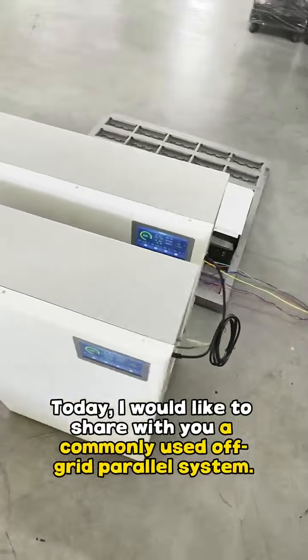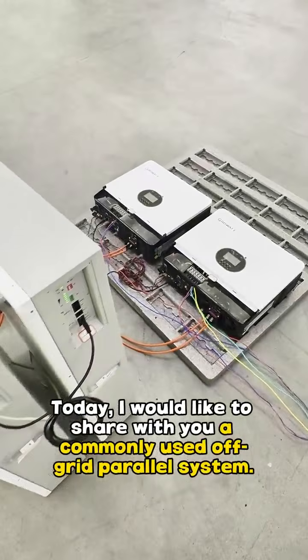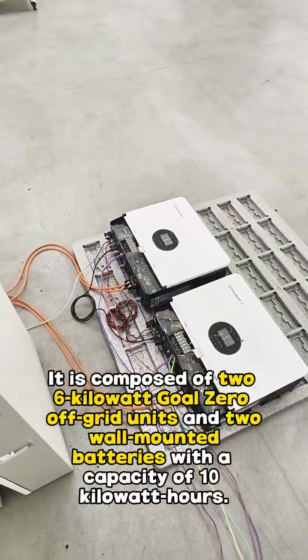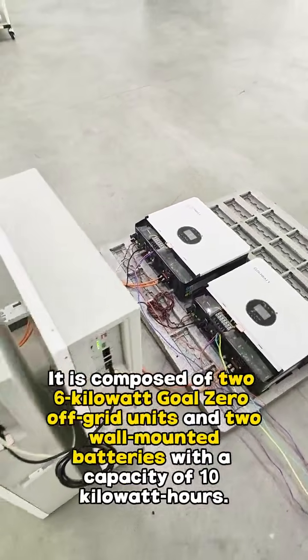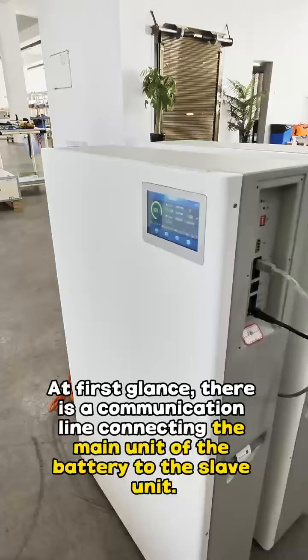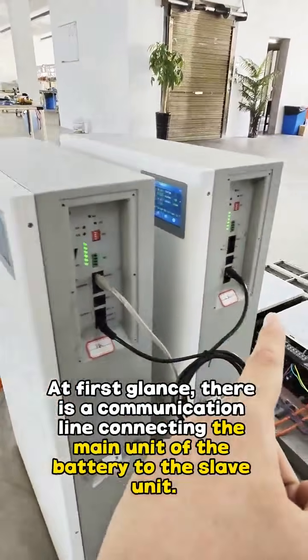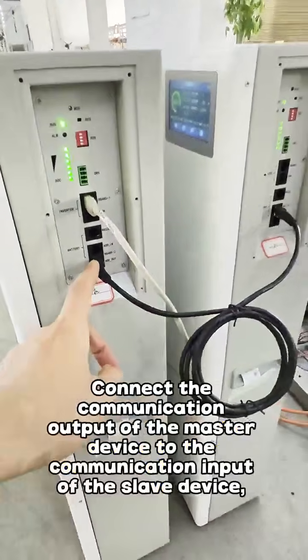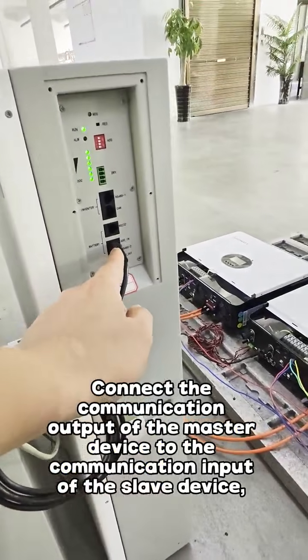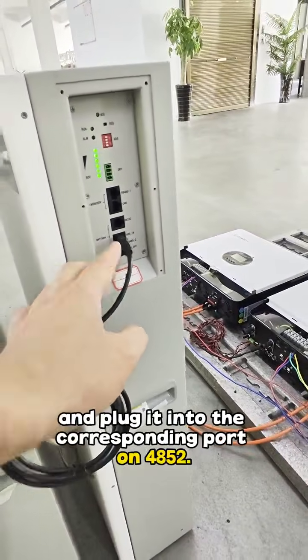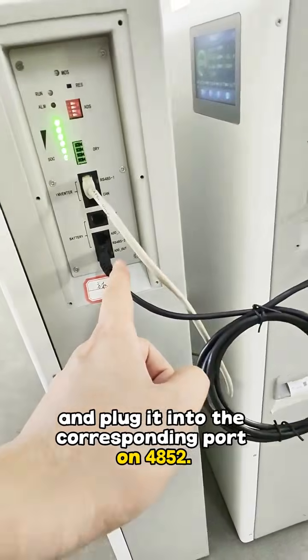Today I would like to share with you a commonly used off-grid parallel system. It is composed of two 6 kW Goal Zero off-grid units and two wall-mounted batteries with a capacity of 10 kWh. At first glance, there is a communication line connecting the main unit of the battery to the slave unit. Connect the communication output of the master device to the communication input of the slave device and plug it into the corresponding port on RS485.